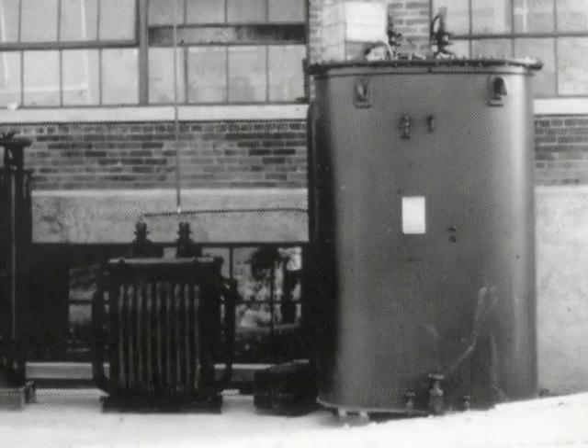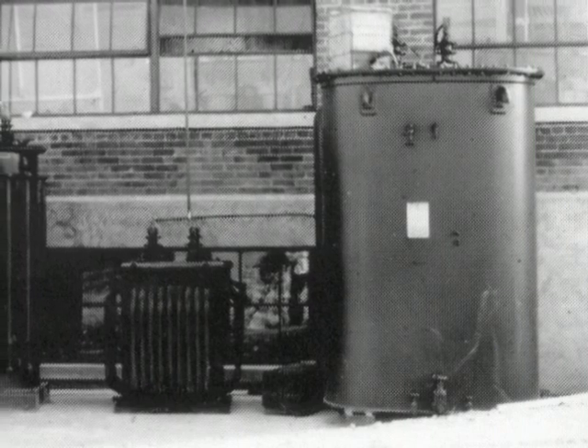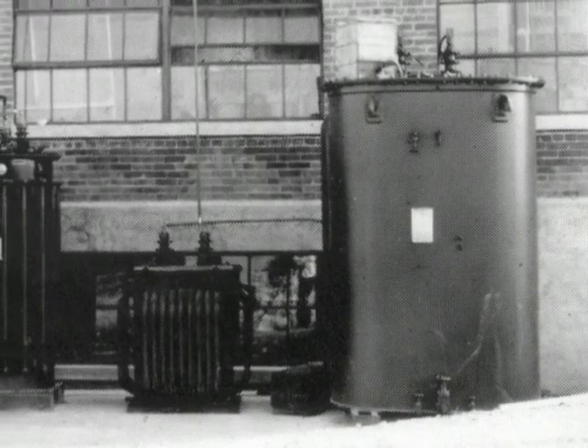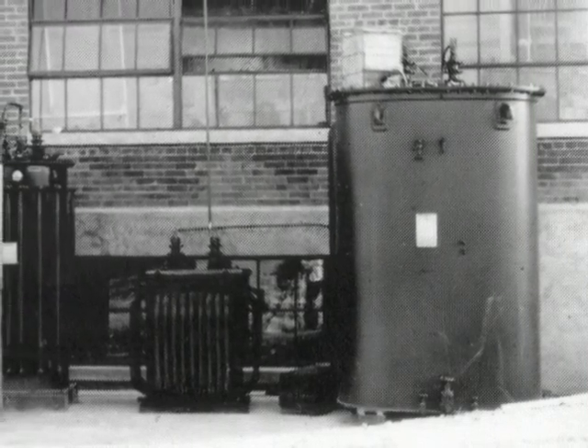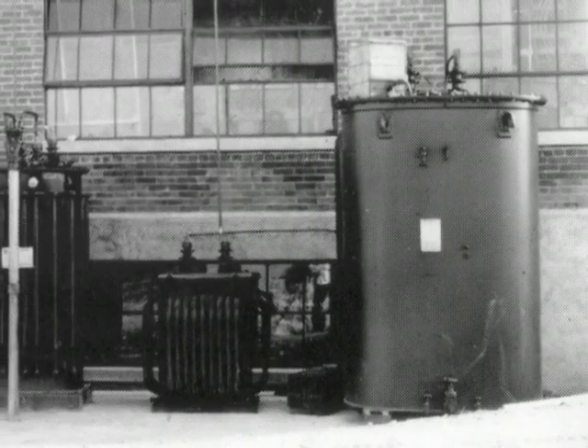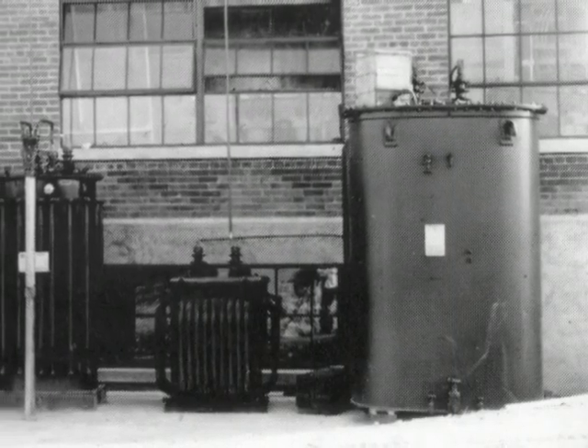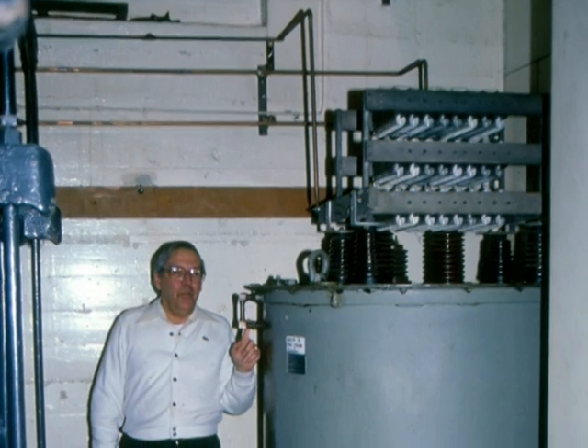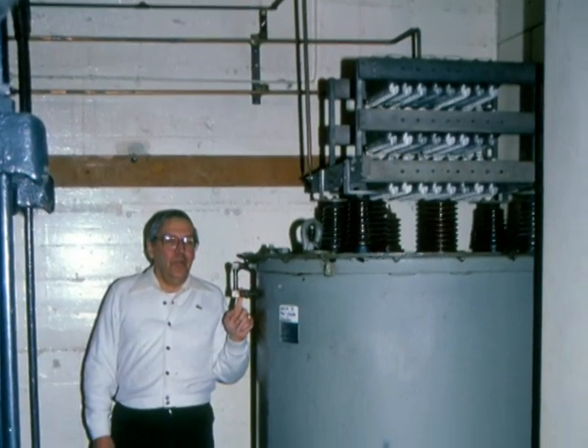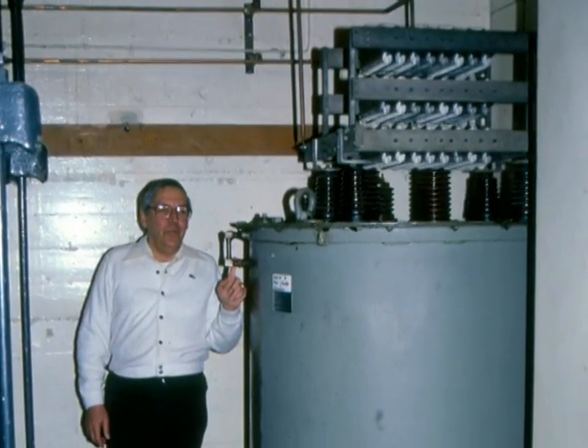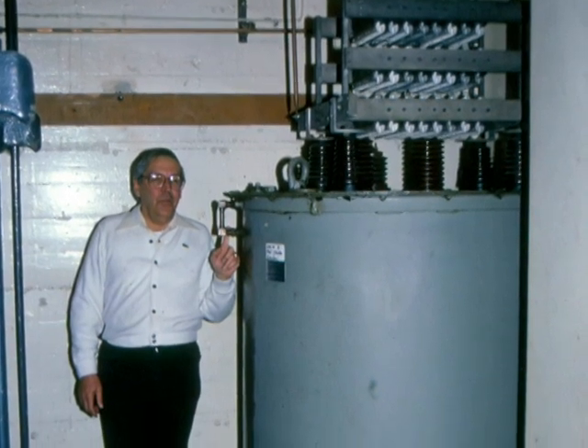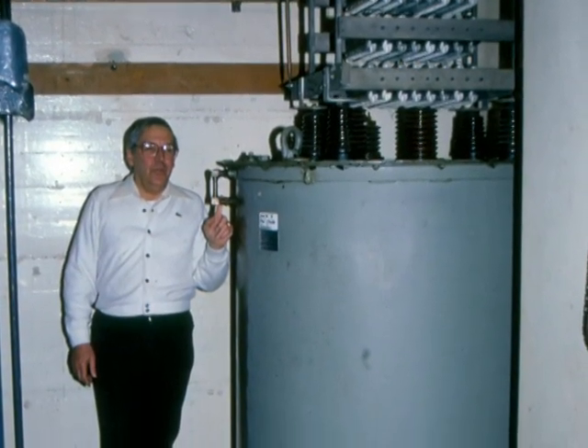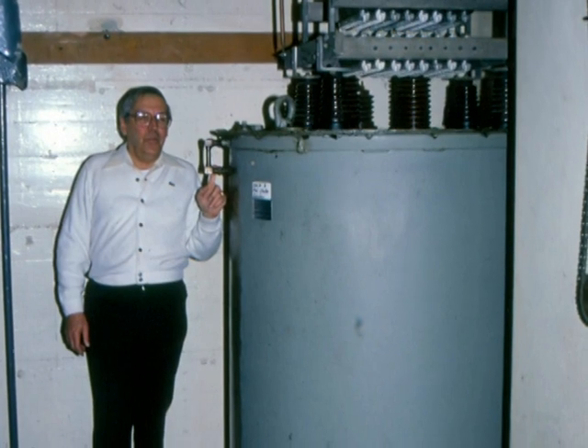The filter reactor was a quarter Henry at 125 amperes. It weighed 3,190 pounds and was cooled with 160 gallons of oil. The modulation reactor was 4.5 Henrys at 60 amperes. It weighed 9,500 pounds and was cooled with 525 gallons of oil.